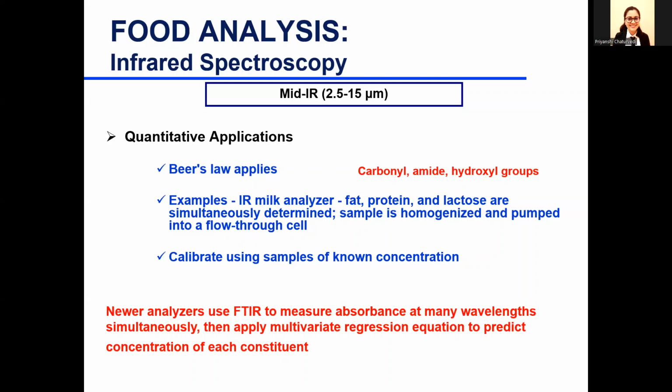If your concentration reads after you've done the chemometrics or the quantification, if it reads like 22% or 25%, that's out of your calibration range, and you either need to get a new set of standards to calibrate up higher, or you need to do something else. That spectral method will not be able to extrapolate and still be quantitatively valid, because it's always dependent on the primary method.